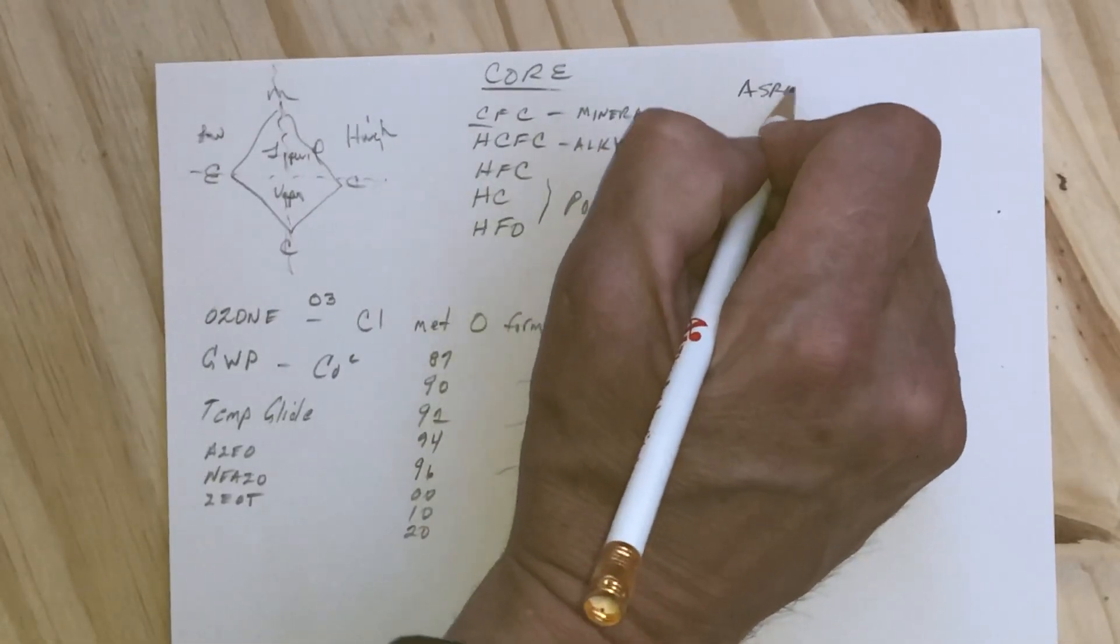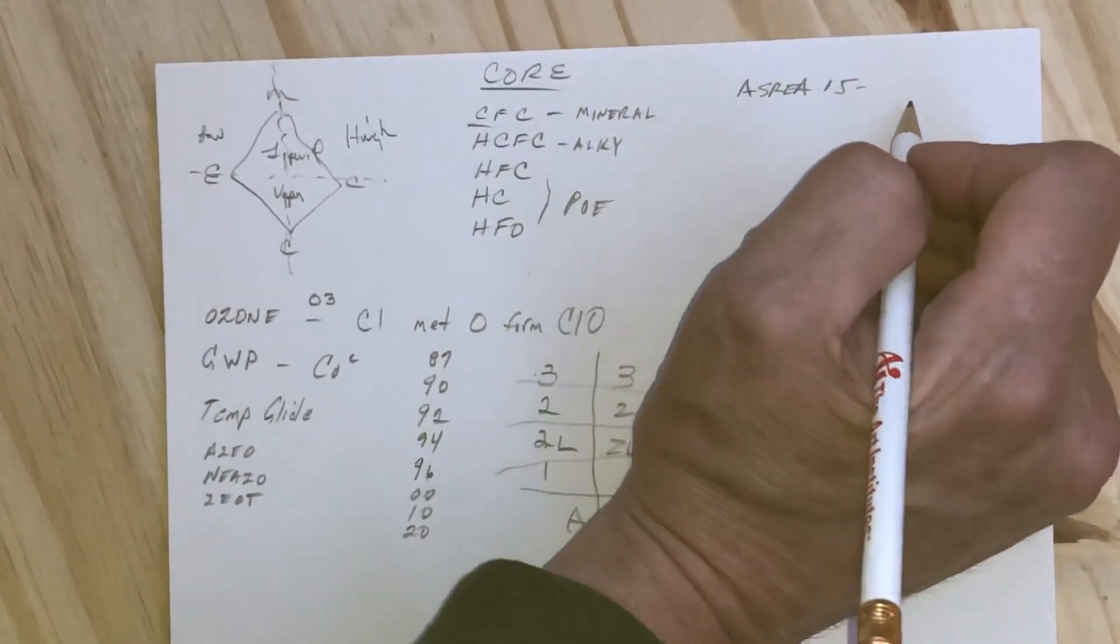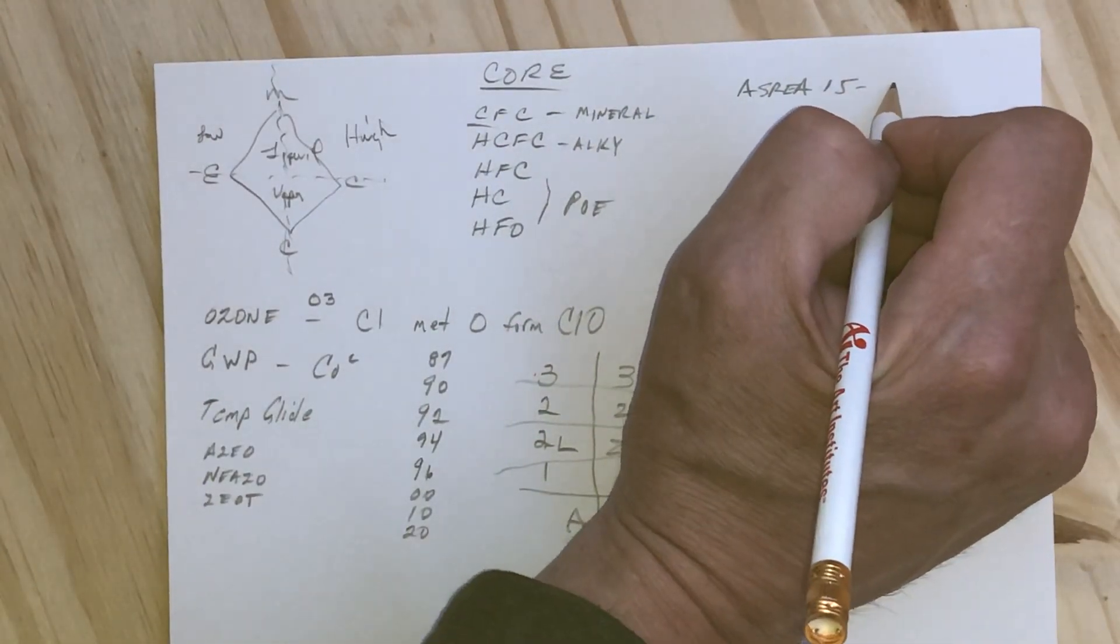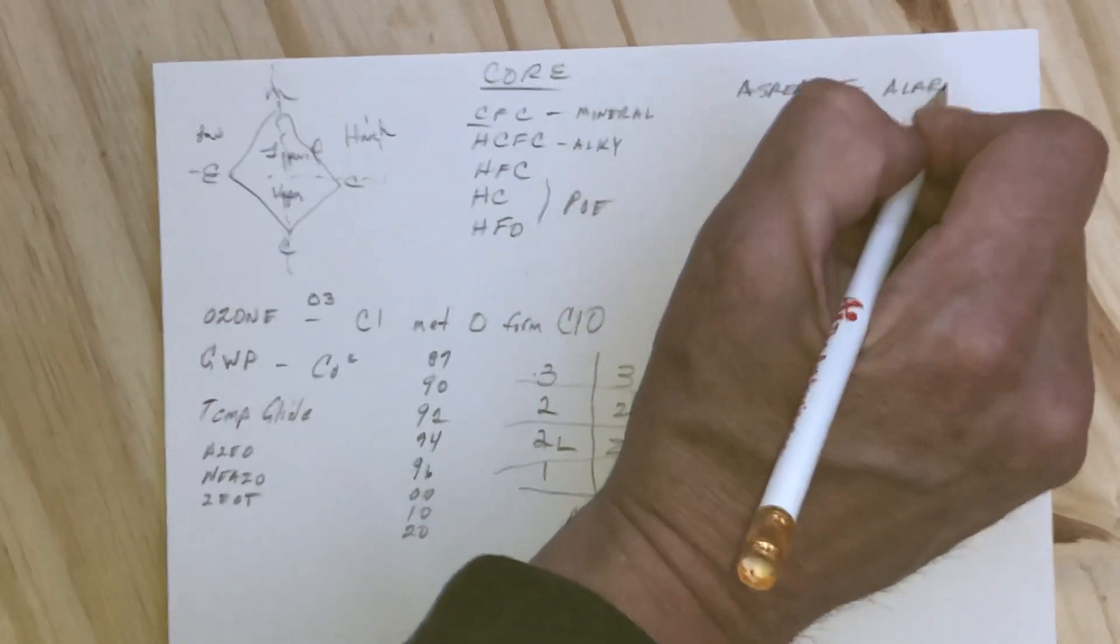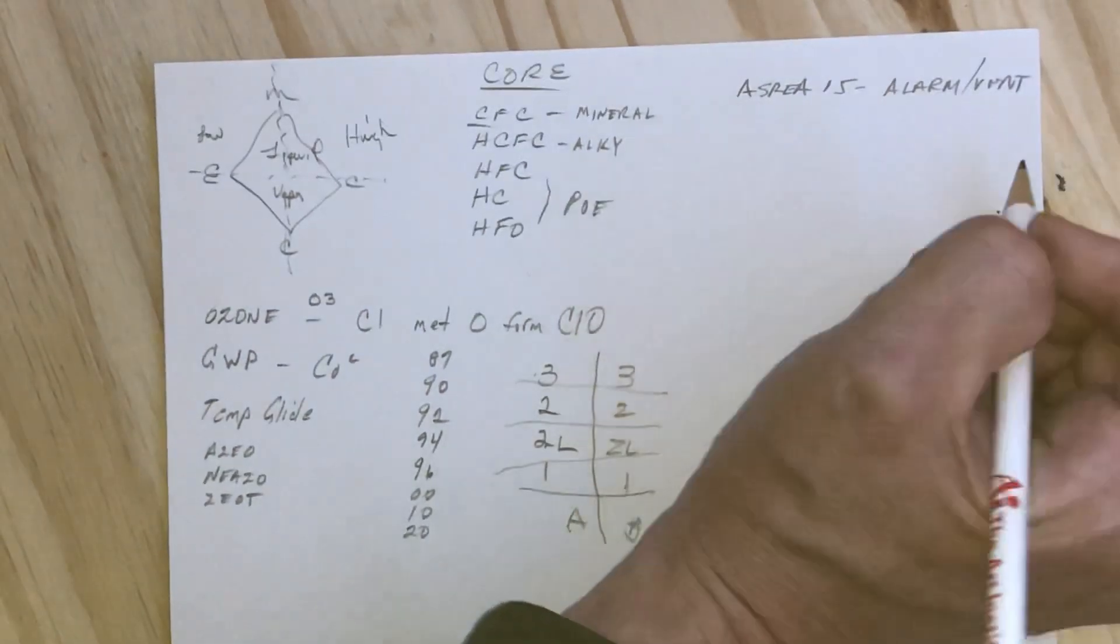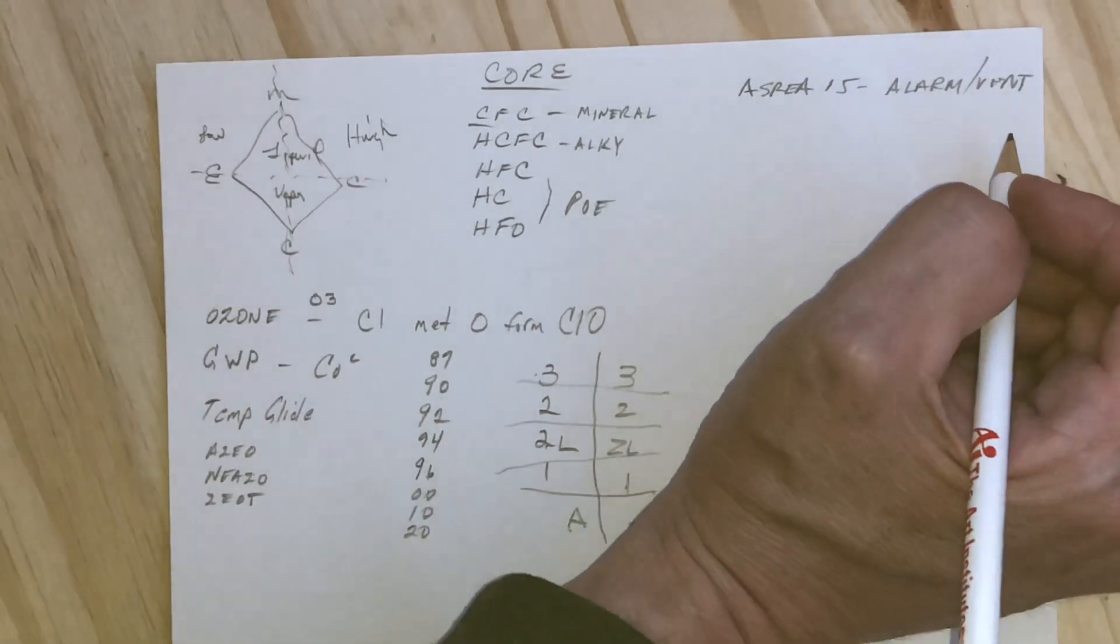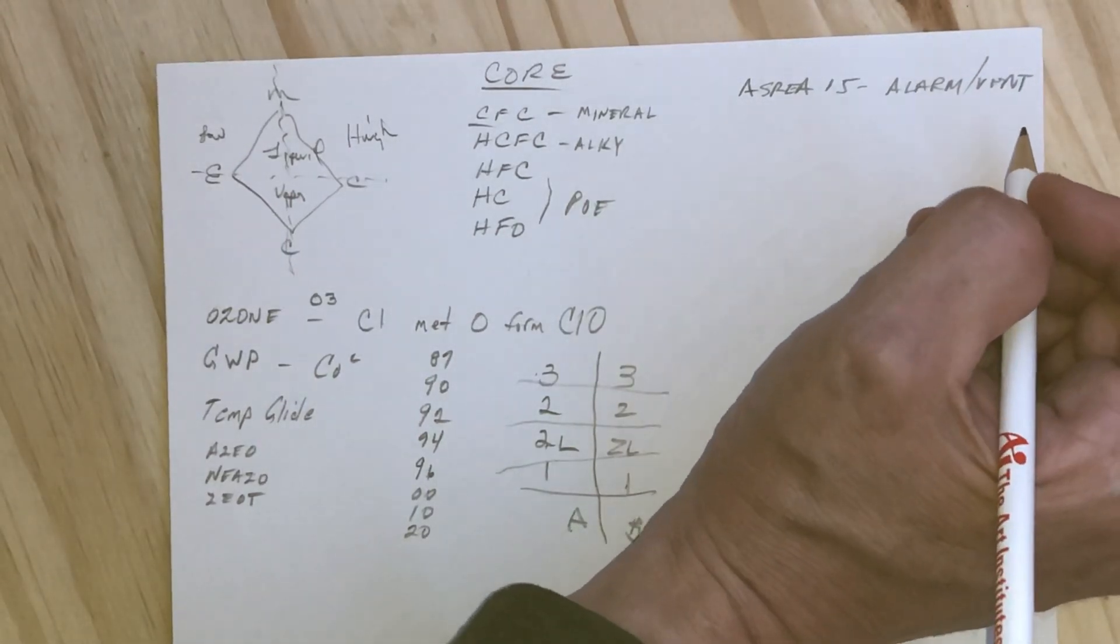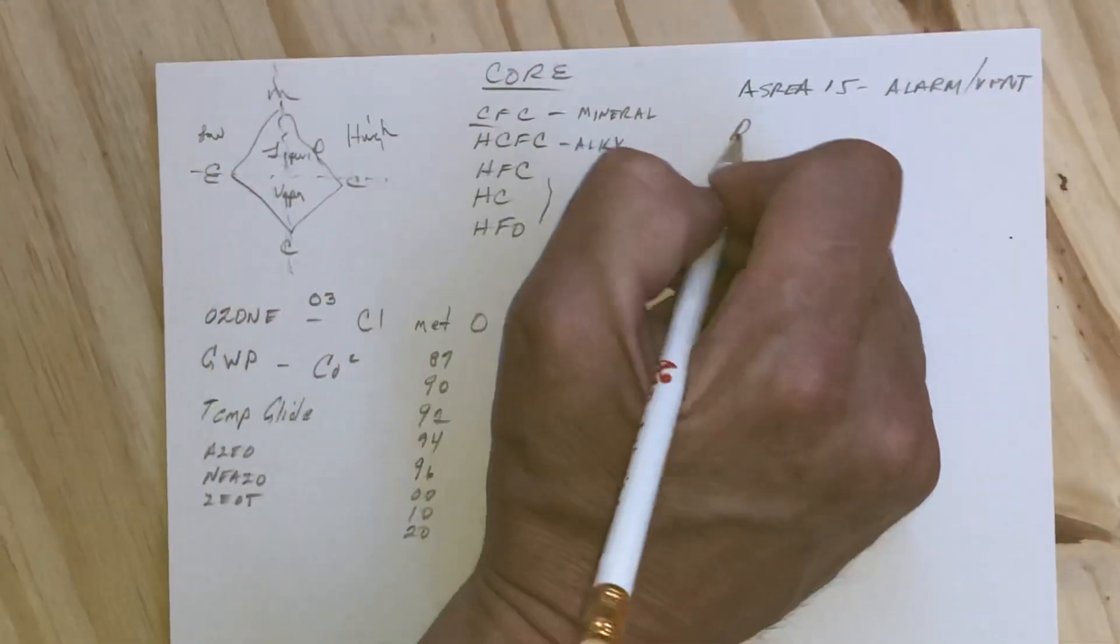Other things you should know: ASHRAE Standard 15 says if we're working with any equipment or room monitors, we should have some sort of alarm set up with a vent and audible tone. If you don't have self-contained breathing apparatus, you should evacuate and ventilate when you hear that alarm.